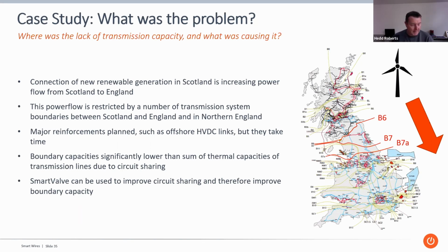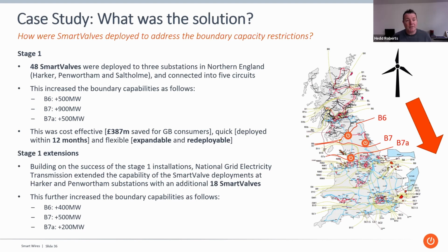So this is the solution: deploy smart valves at substations in the north of England so that circuit sharing is improved, and as a result boundary capacity is increased. The stage 1 deployment was 48 smart valves across 3 substations in northern England - Harker, Penwortham and Saltholme. At those substations, the smart valves were connected into 5 separate circuits. That initial deployment increased boundary capacity of B6 by 500 megawatts, B7 by 900, and B7A by 500.